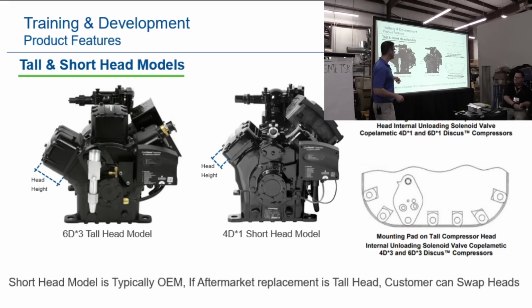Short and tall heads on the Discus. So OEMs, short head models are typically OEM. If the aftermarket replacement is a tall head, the customer can swap the heads. So if you have a failed compressor, right, and you have short heads on it, and the service one comes with the tall heads and it doesn't fit, you can take these small heads and put them on there. Okay? It's a little tip.